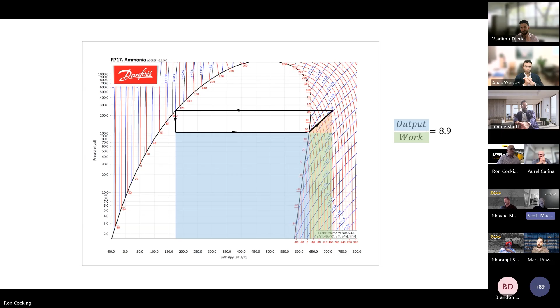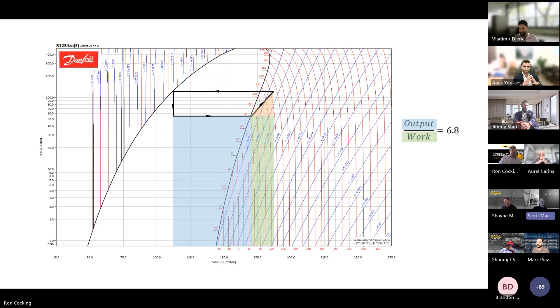this is the exact same capacity equipment, only using R1234ZE. We can see that our coefficient of performance is reduced to 6.8. And what that means at the end of the day is that the R1234ZE option will require 31% more energy than the R717 ammonia package to do the exact same amount of cooling. Slide, please.